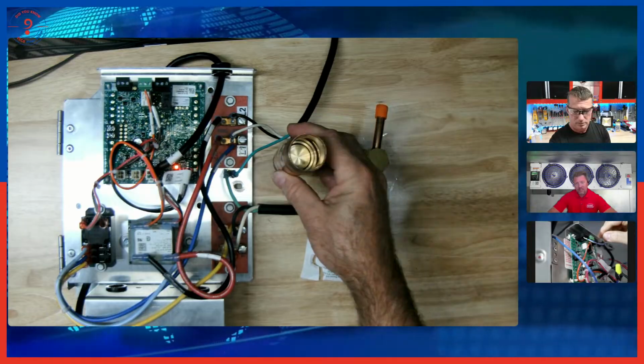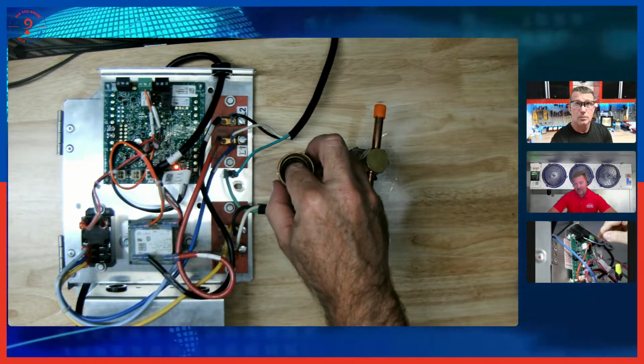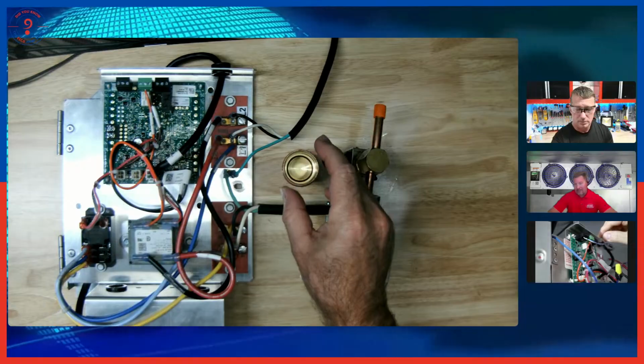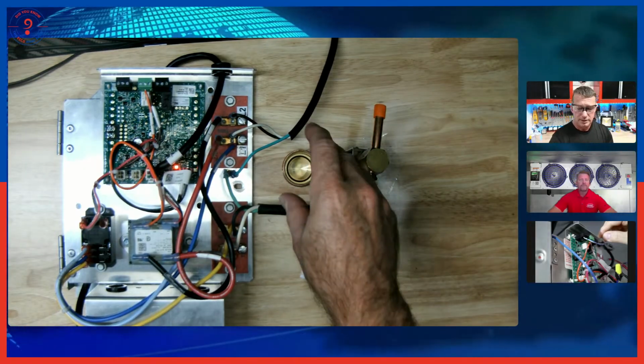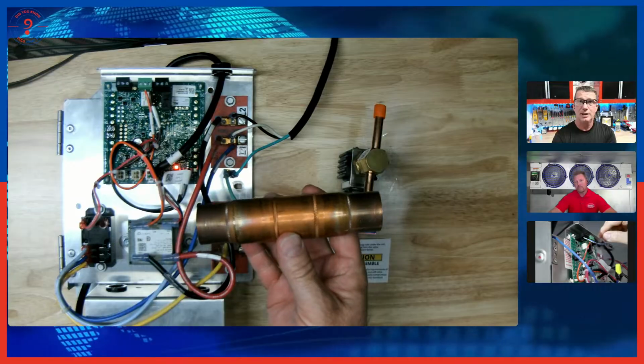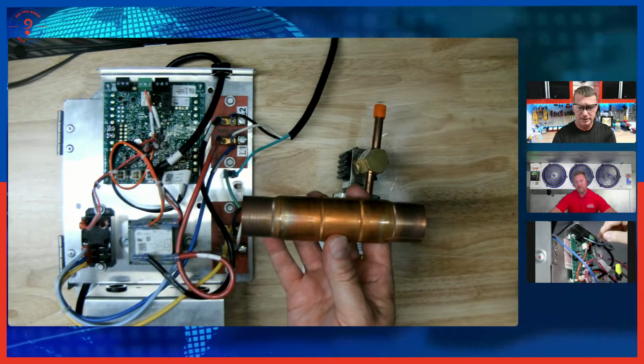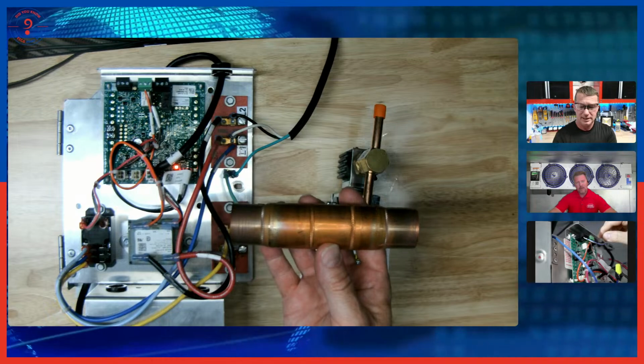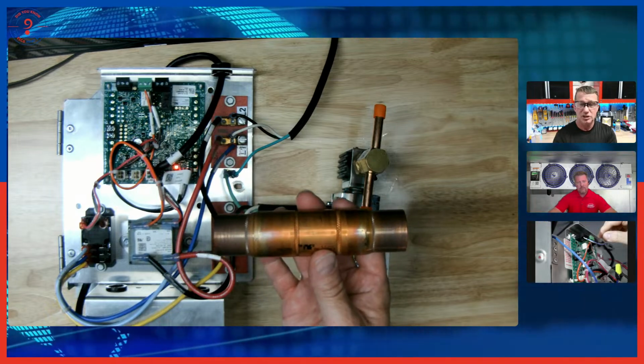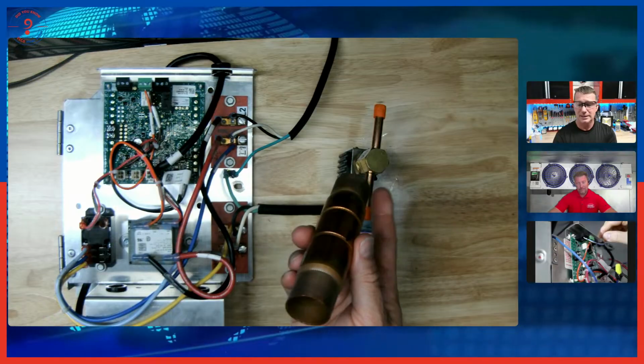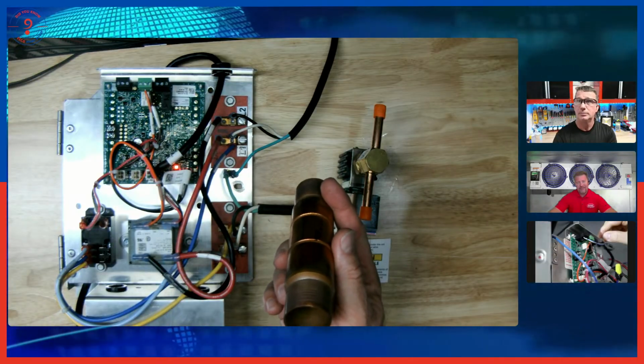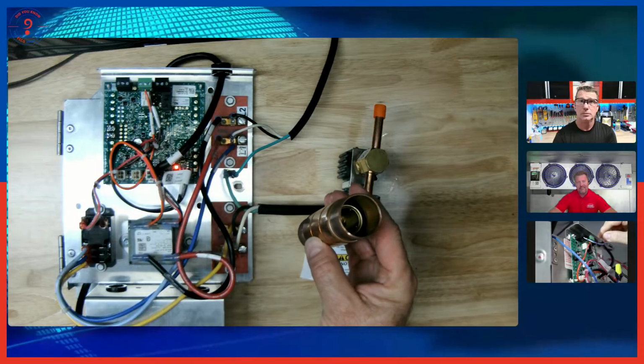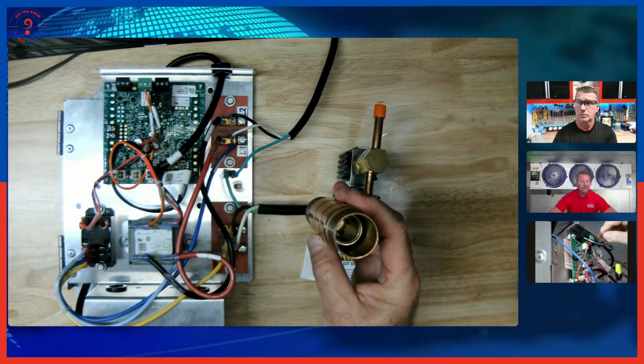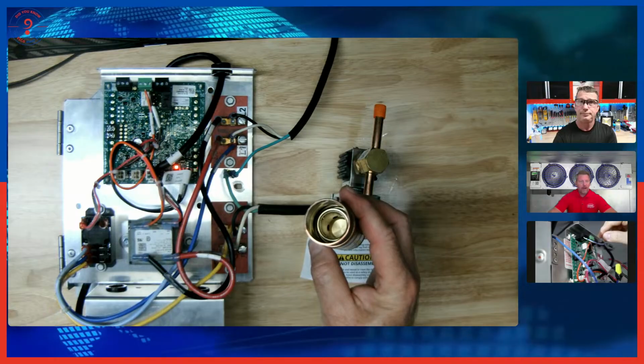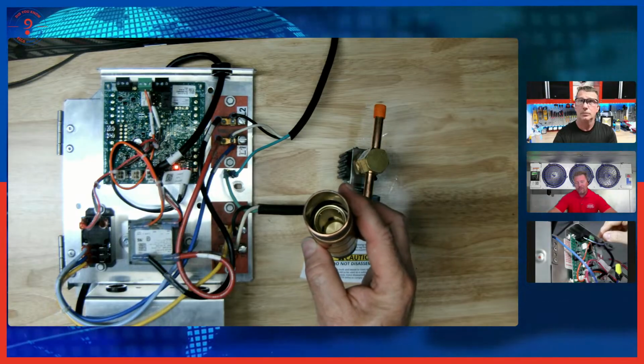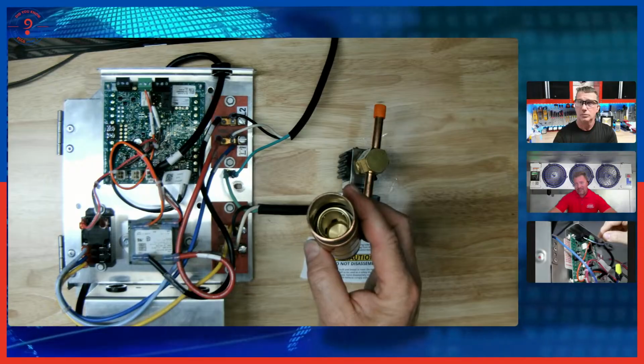So both of those are UL mandated for A2L refrigerants. You can't do one or the other. Both are required. And you've done a really good job with this check valve. I mean, it's really not significantly different than the line itself. Some of our previous generations of check valves were kind of monstrosities. And yeah, no, these are nice and tight. You're not going to stick out like an eyesore, or be something that requires you to repipe your suction line by much to put it in there on an existing install.